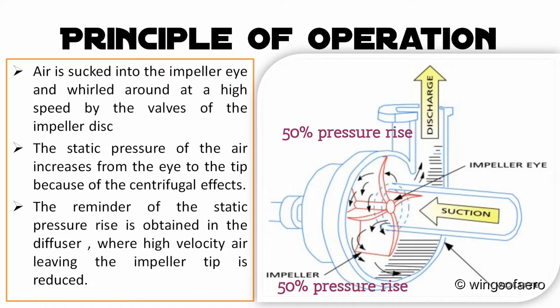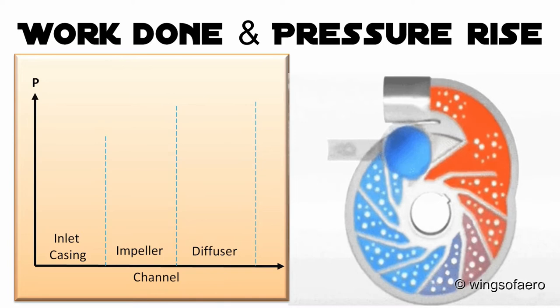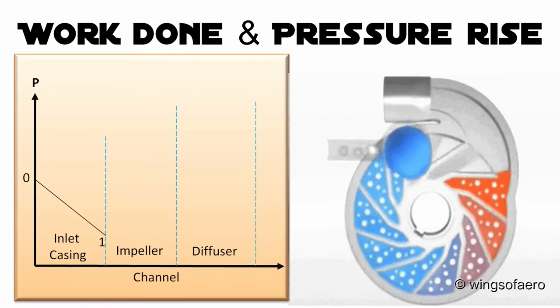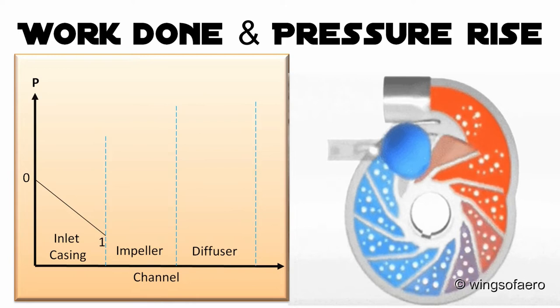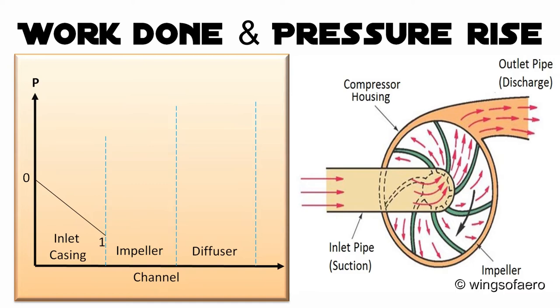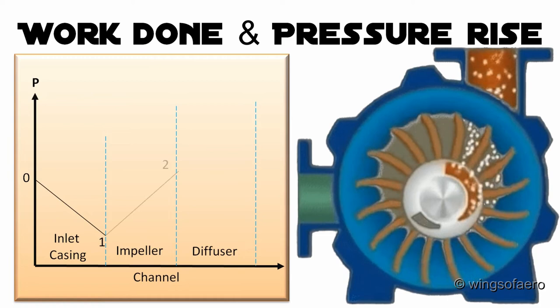The contribution of each component of the compressor in producing the pressure rise in the stage is shown in the figure. The inlet casing with acceleration nozzle directs the airflow into the impeller eye or inducer. Since the velocity of air increases as it approaches the eye, its static pressure decreases accordingly. In the impeller, the blades impart a swirling motion to the air, which leaves the impeller tip at a very high velocity.